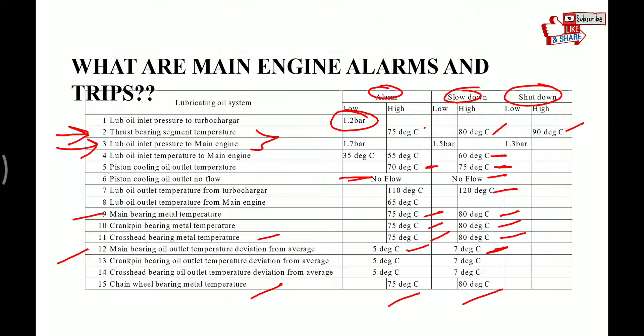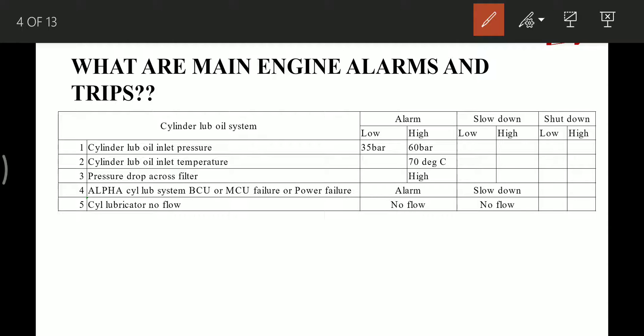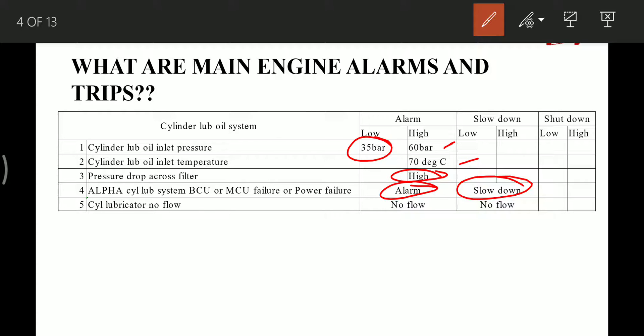The cylinder lube oil system: cylinder lube oil inlet pressure gives a low-low pressure alarm at 35 bar and high pressure alarm at 60 bar. Cylinder oil inlet temperature gives a high temperature alarm at 70°C — no low alarm. Pressure drop across filter gives a high alarm. If the alpha lubricating system is fitted, backup unit or main control unit failure or power failure gives alarm and slows down. Cylinder lubricator no-flow gives alarm and slows down the main engine.